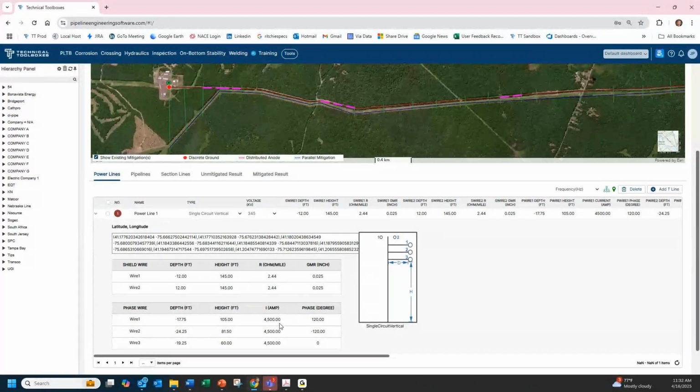And then what I did, since this has some reconducting, is instead of the typical peak current, in this case instead of 1500 amps, this happened to be 4500 amps. So we're saying, wow, I've got more challenges here. Well, you do, but you have more tools to address those challenges very easily and to mitigate this. And this is what we're talking about.